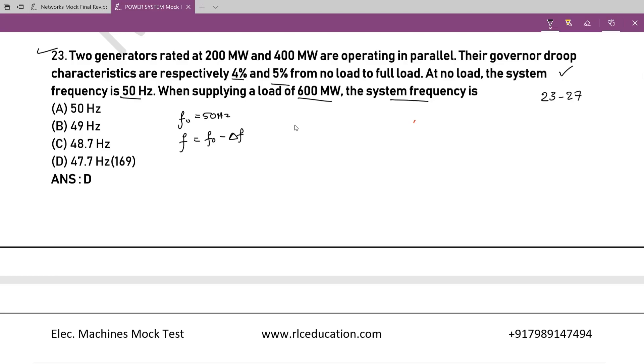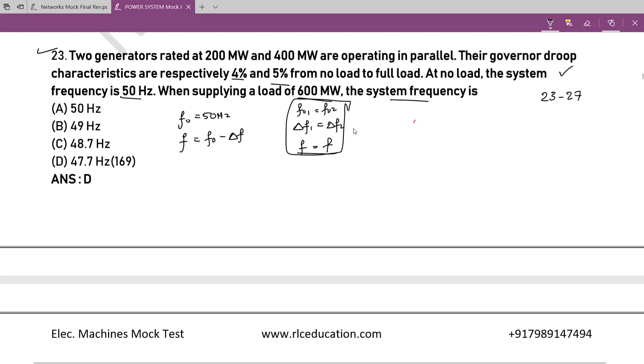Since both generators are in parallel, both will drop by the same amount — that is, Δf₁ = Δf₂. Both generators are at the same no-load frequency because they are in parallel, and even after load is applied, the final frequency of both generators will be the same. This is the condition for parallel operation. The speed regulation constant is given by Δf / ΔP.